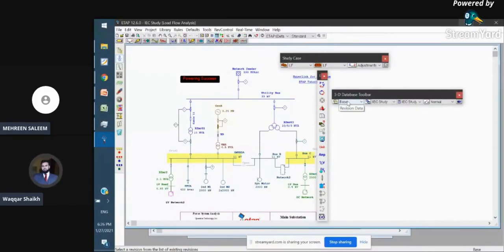This option is also sometimes useful when we are doing arc flash analysis, where we want to see the behavior of the protection settings. By changing the protection settings on the arc flash levels, we put one type of protection settings under one revision database, and another type under a different revision database. Switching between these revision databases lets us check the behavior of the network arc flash levels for different relay settings, based on engineering requirements.